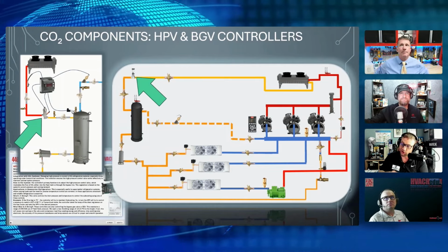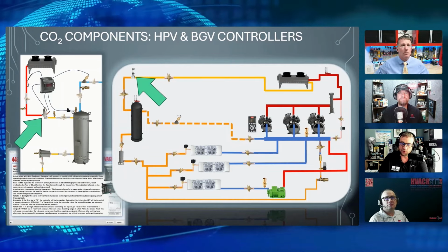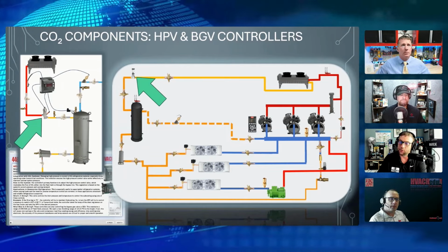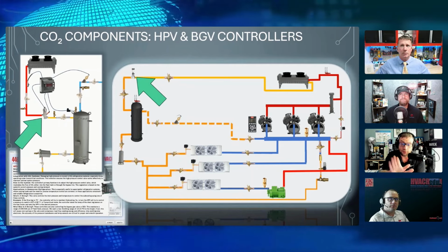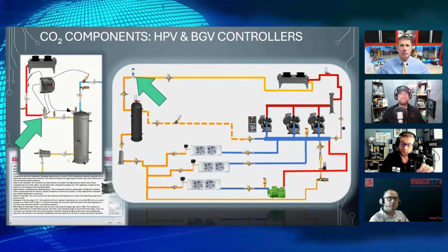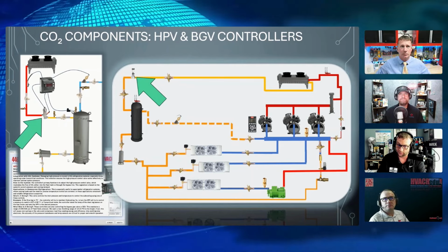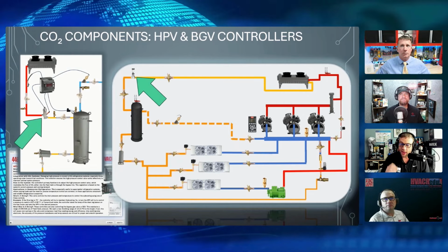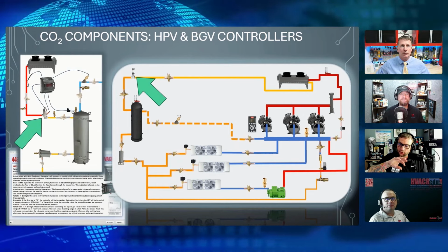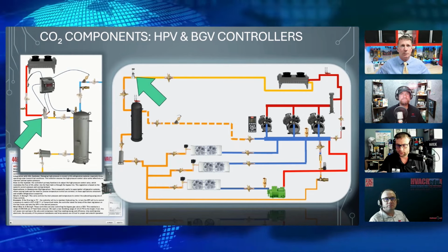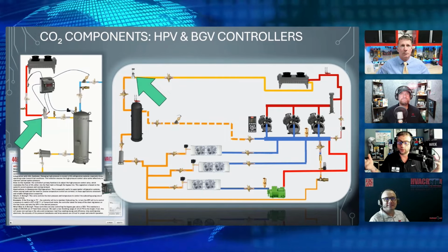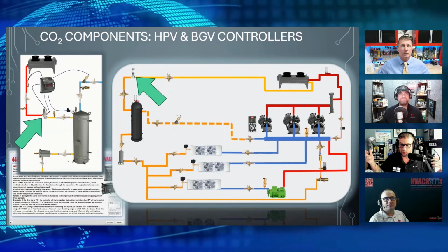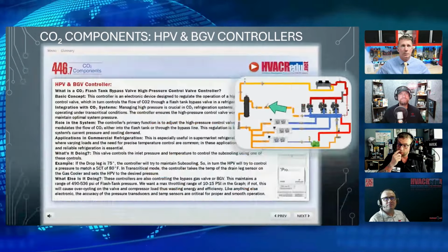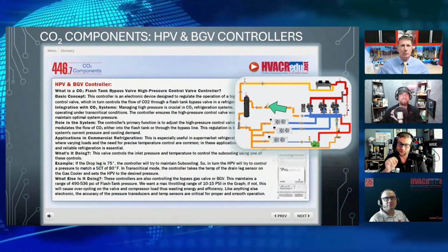Now, we still have a flashing effect going off. So even though we have, you know, probably 100% liquid backed up into that line, we're still going to flash off when that thing opens up, right? But for all intents and purposes, we have liquid on the inlet of that valve. Then when it goes into transcritical function, because like I said, Schrodinger's cat, we don't know. Is it a liquid? Is it a gas? Is it a vapor? Plasma? We don't know what it is. So the operation of this thing changes just a little bit.